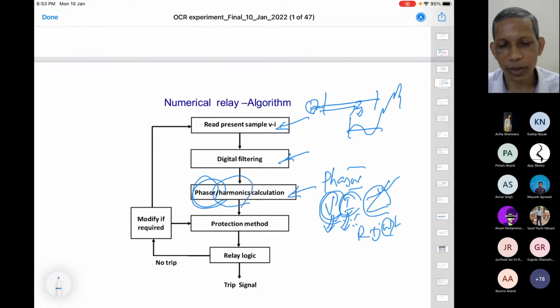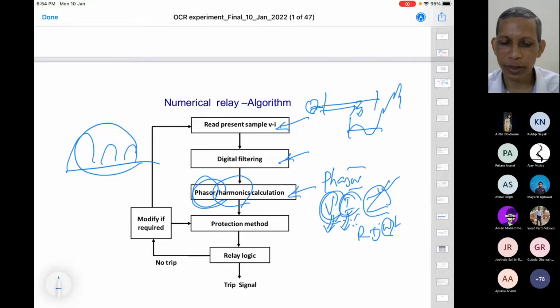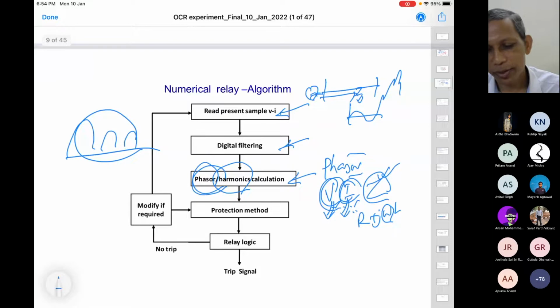Sometimes the harmonic components are also required, particularly in transformer protection, in the inrush situation. Whenever we switch on the transformer, the inrush current flows 5 times, 10 times the normal current, without loading also on the secondary side. That current is not detrimental, but that is not a fault situation. So even though the current is high, the relay should not trip. To distinguish whether this is inrush or not, harmonics are estimated. The current pattern becomes like this, not symmetrical along the x-axis, the time axis. So this contains a lot of second harmonic component. If you estimate the second harmonic component with respect to the fundamental, then you can make a judgment that yes, this is an inrush situation, not a fault situation. So that's what the relay does.